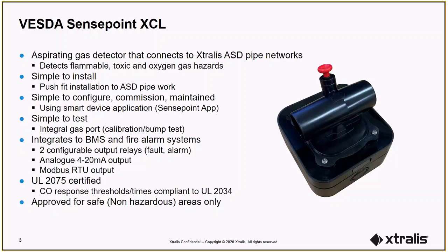It has two configurable relays, 4 to 20 milliamp analog or Modbus RTU outputs for integration to BMS, fire alarm systems, PLC systems. It is UL 2075 certified, which means it is compliant to the carbon monoxide response thresholds and time requirements of UL 2034. Finally, it is designed only for safe areas, and cannot be installed within or monitor hazardous areas.